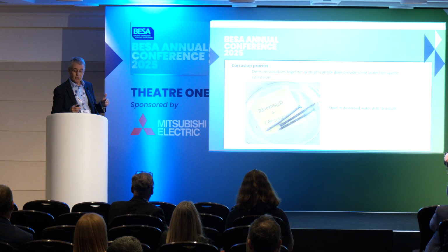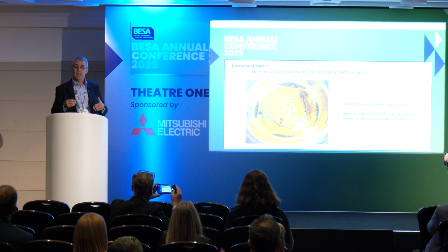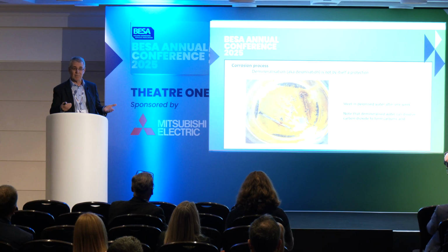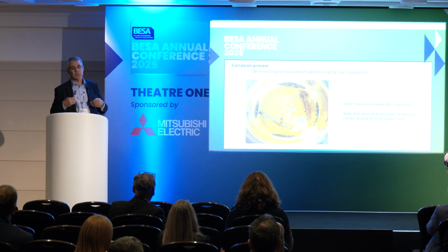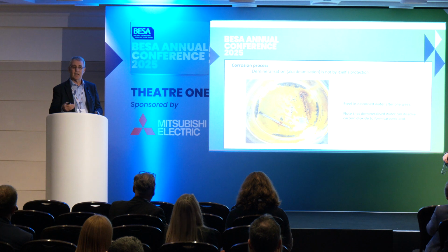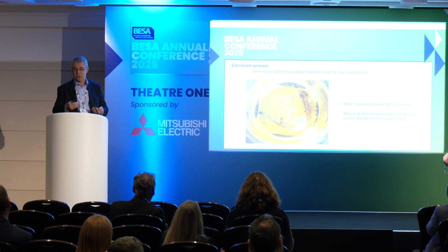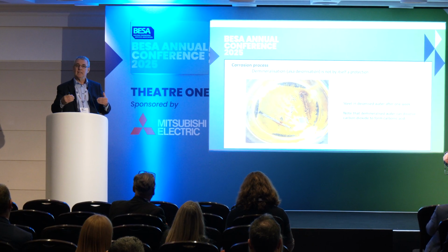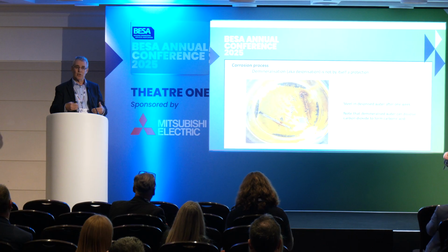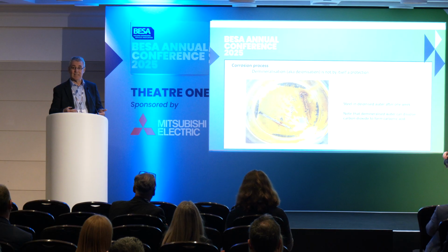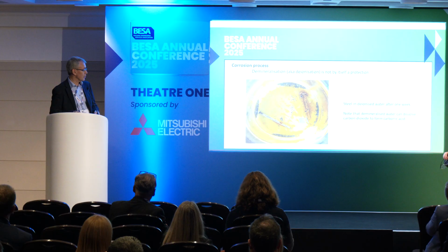But if you switch to deionized water by itself, or demineralized water, same thing. That in itself is not a protection, because demineralized water can still have high oxygen levels. It's got lower conductivity, which in theory will give you some stifling of corrosion. But the trouble with demineralized water is it can dissolve carbon dioxide from the atmosphere, which can cause it to become acidic. And once it becomes acidic, then it will still drive corrosion. So demineralized water by itself is not a good prevention method.